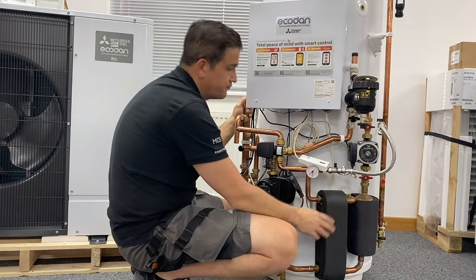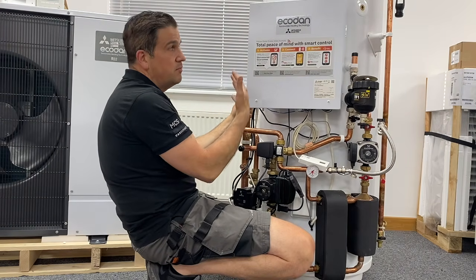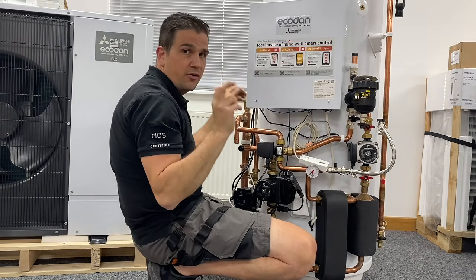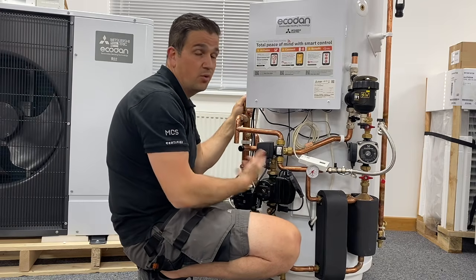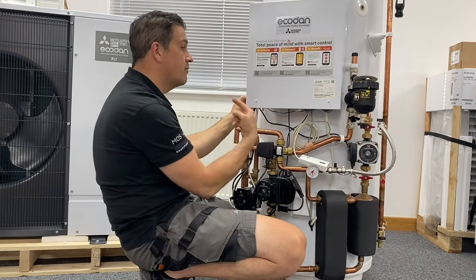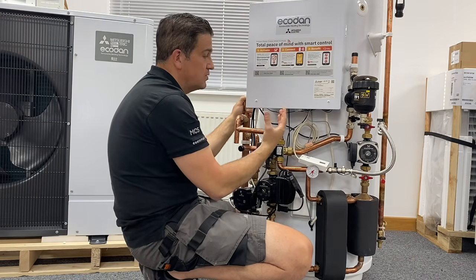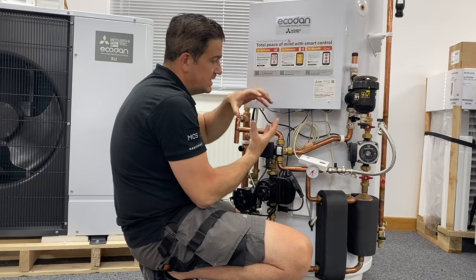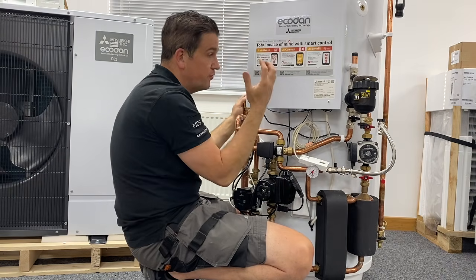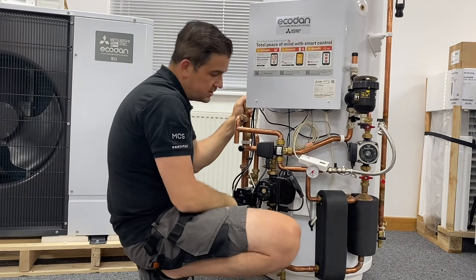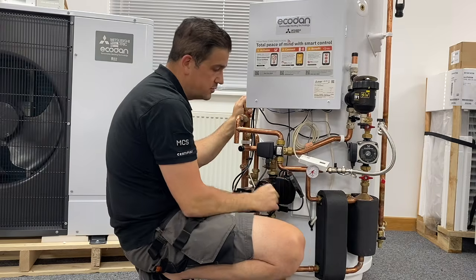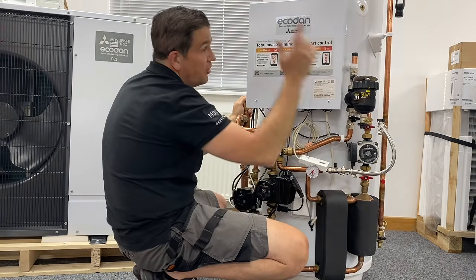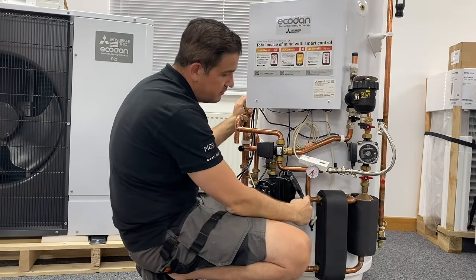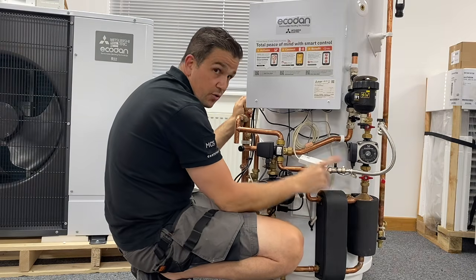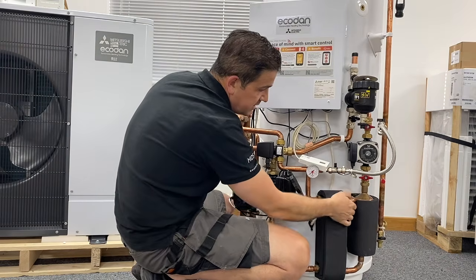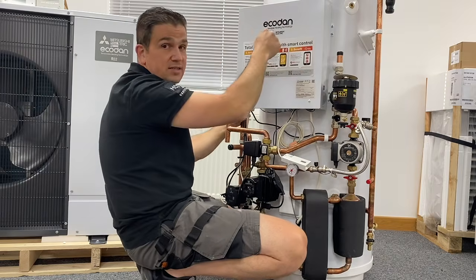On here we've got a heat exchanger. Now a conventional hot water cylinder, if you're using what we call indirect, so with a heat source, whether it be a boiler or a heat pump, generally you'd have a coil going round in a big spiral inside the cylinder, and that is what's getting heated up, a bit like a radiator, and it heats the hot water inside. Now, this uses a slightly different technique, very similar to a thermal store type situation. It's not a thermal store, but it has a heat exchanger here. The hot water generated from the heat pump will cycle in and go through this heat exchanger, and on this side is your heat pump medium, and the other side will get put into the hot water cylinder and come back out.